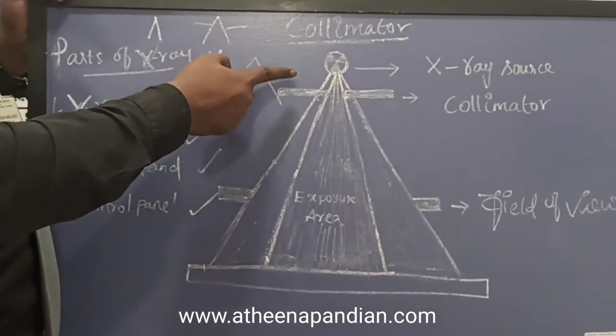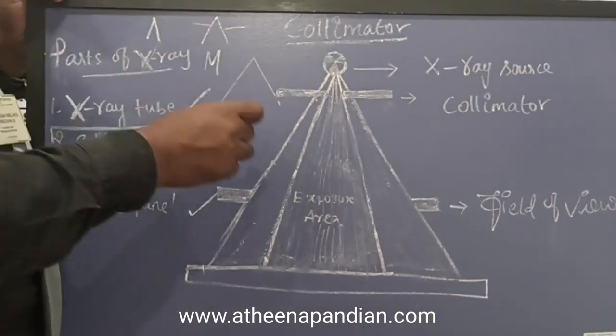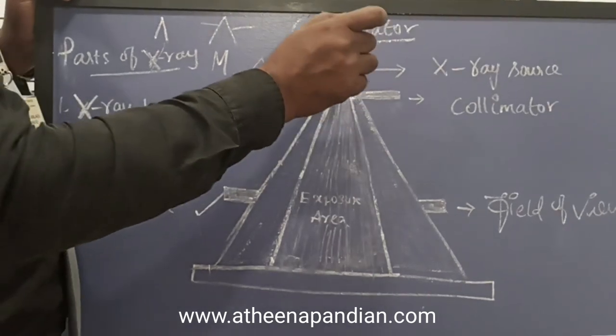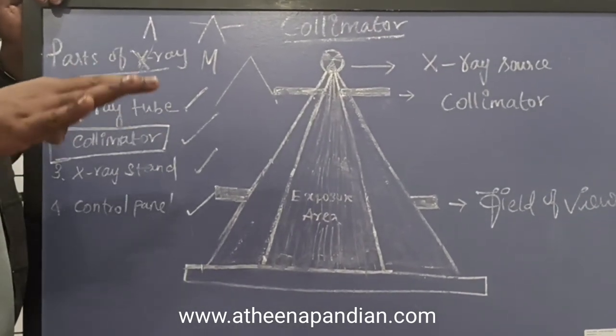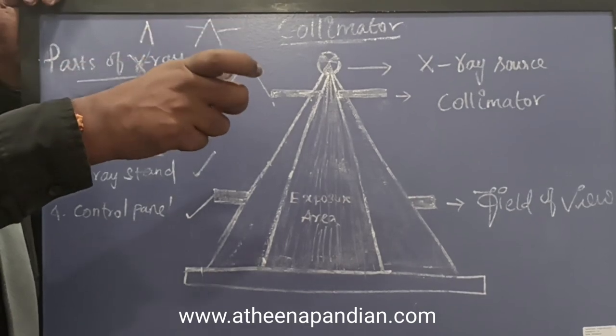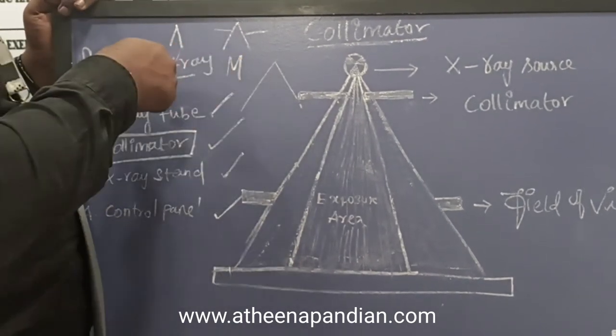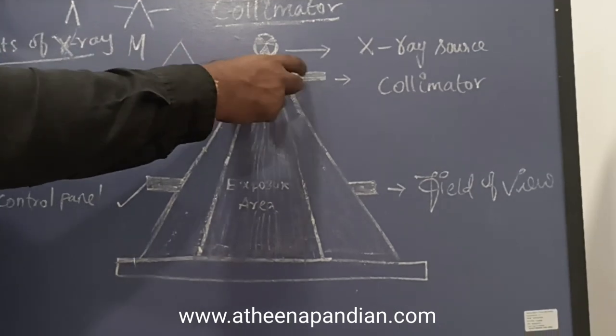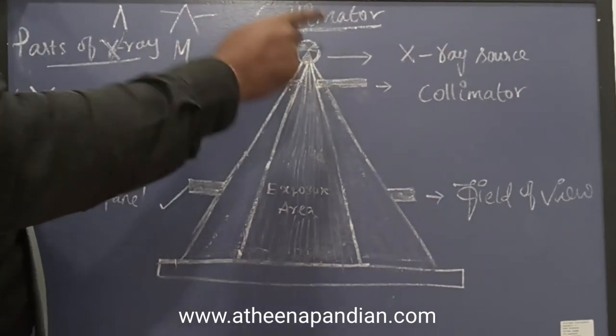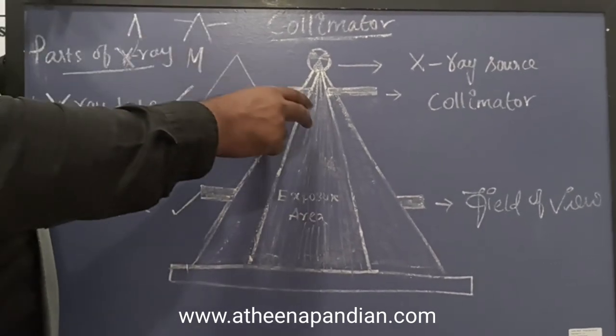The collimator is purposely helpful for finalizing the width of the X-ray source. The reason we control the width is: for example, if the doctor needs to take only the elbow, knee, or wrist region, a small amount of width is enough. But if the doctor asks for a chest X-ray, the width needs to be very high. During that time we need to adjust the collimator to increase the width of the X-ray source. Through this collimator we can adjust the width of the X-ray source.